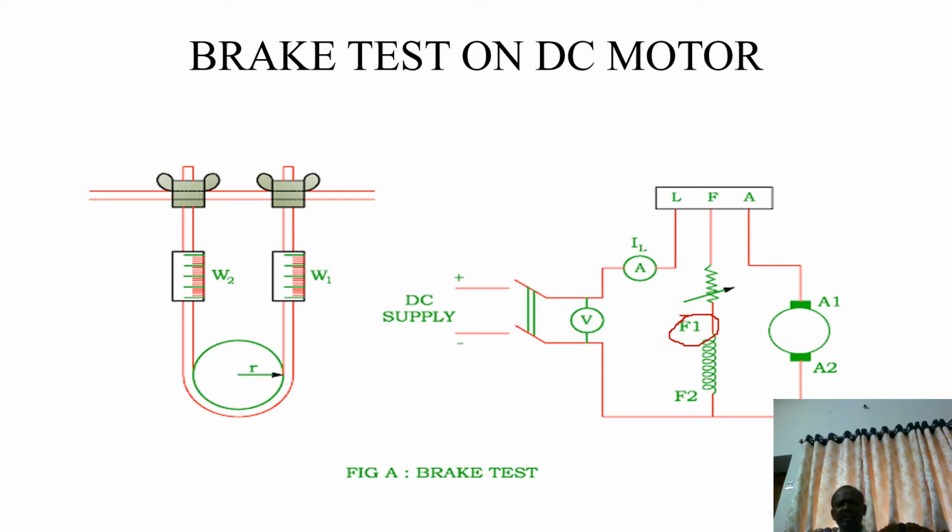So this is the observation under no load condition. When the pulley is connected across the brake drum of this motor, by varying this, the load is increased. When load is increased, speed decreases and load current increases. So here load current is inversely related to the speed of the armature. We note the readings; V is always constant. By variation we observe another ammeter connected in series with the field, which notes the field current.